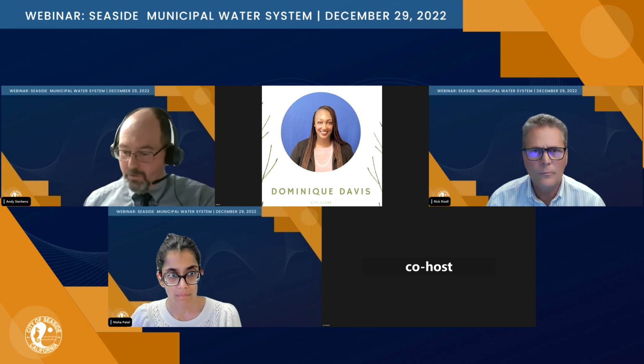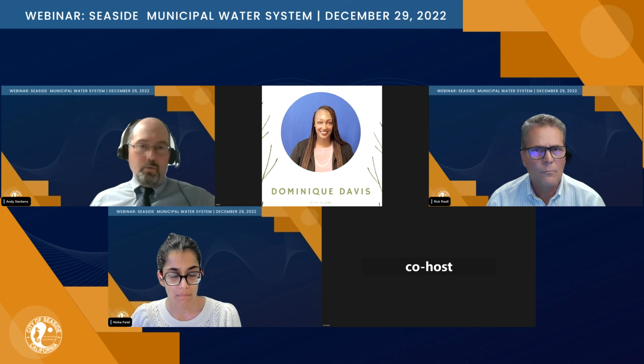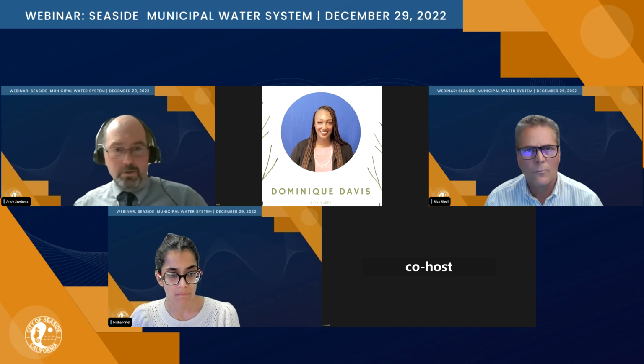Post a response. Obviously, I don't know if this particular well has it, but some wells have what's called a deep well control valve, so that when the pump first turns on, the water is discharged to the storm drain, and the valve slowly opens up to convert the well from discharging to the storm drains to discharging to the distribution system, and that prevents a pressure surge in the distribution system. And similarly, when the well shuts down, the valve diverts the flow to waste first, and then the pump turns off. But those are normally piped to either a percolation basin or the storm drain system. It wouldn't be discharging to the street. So we'll have to have operations look at that.